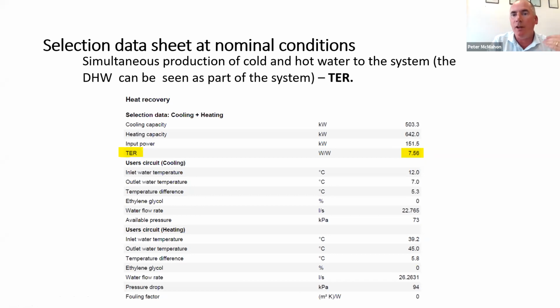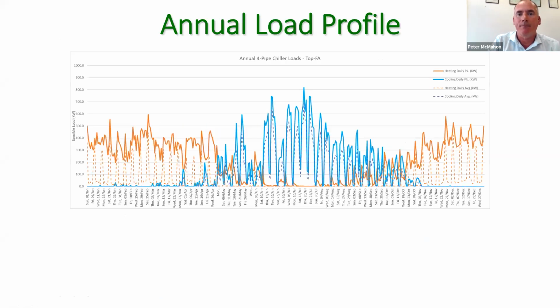But again, just to show you in reality what you can achieve. Now, everything I spoke about there was talking about 100% input, 100% output. We know that loads change throughout the year. So certain process cooling applications have a consistent load in factories, mushroom farms, other horticulture applications. The load is going to change often in conjunction with the ambient temperature changing. So we'll often see a profile where the heating demand drops in the summer, goes up in the winter. And of course, the complete opposite, their cooling demand will increase, peak in the summer and back down in the winter.